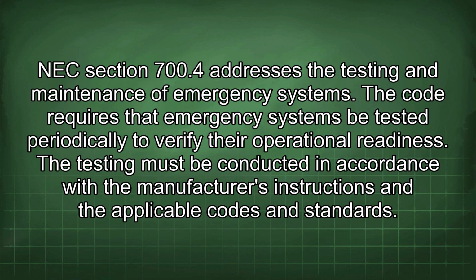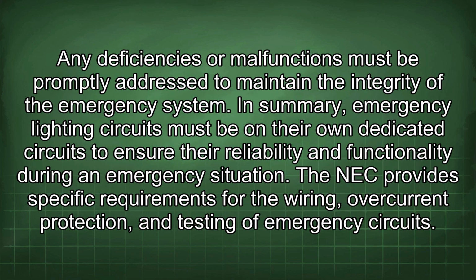NEC Section 700.4 addresses the testing and maintenance of emergency systems. The code requires that emergency systems be tested periodically to verify their operational readiness. The testing must be conducted in accordance with the manufacturer's instructions and the applicable codes and standards. Any deficiencies or malfunctions must be promptly addressed to maintain the integrity of the emergency system.